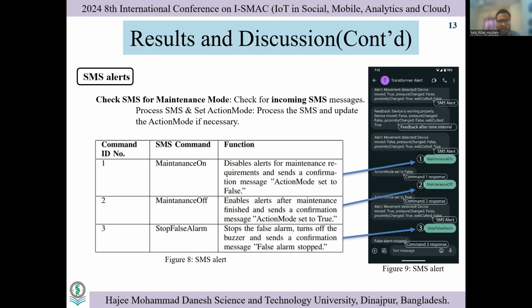As shown in the table on the left side, there are three main SMS commands. The command maintenance on disables the alert during routine maintenance and sends a confirmation message, action mode set to false, ensuring that no unnecessary alarms are triggered during the maintenance period. And once the maintenance is complete, the maintenance off command re-enables the alert and gives a confirmation message, action mode set to true, bringing the system back into the active monitoring state.